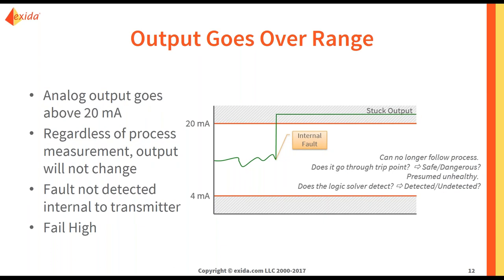Now let's say your output goes over range — your analog output goes above 20 milliamps. Regardless of the process measurement, your output will not change, so it is no longer following your pressure, temperature, flow, etc. The fault is not detected internal to the transmitter. This would be called a fail high. Without knowing your trip point, we don't know if this is a safe or dangerous failure, or if it is detected or undetected, without knowing how your system is configured. We will go into that later.